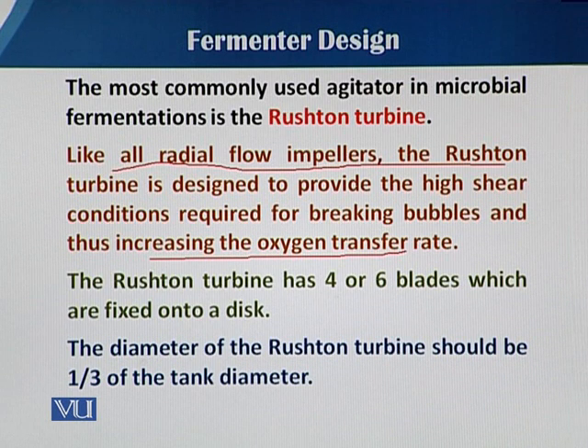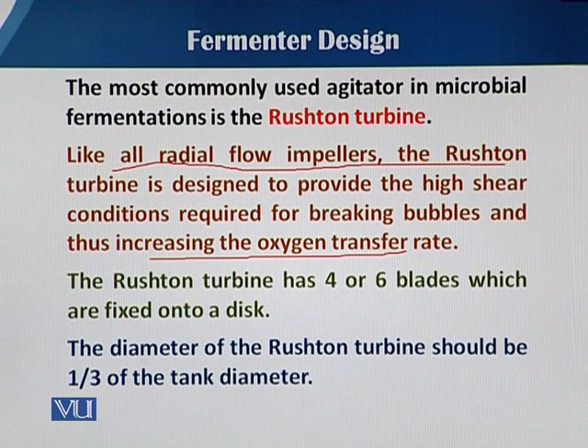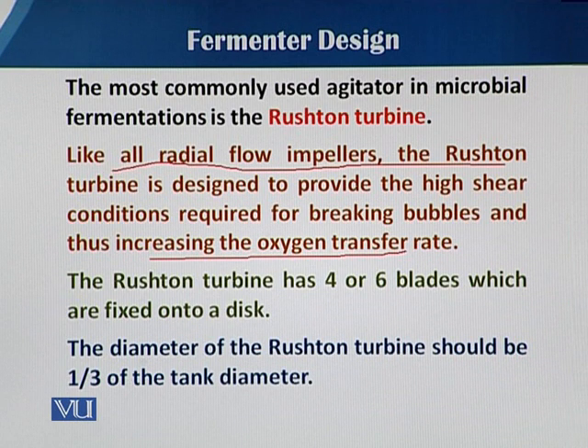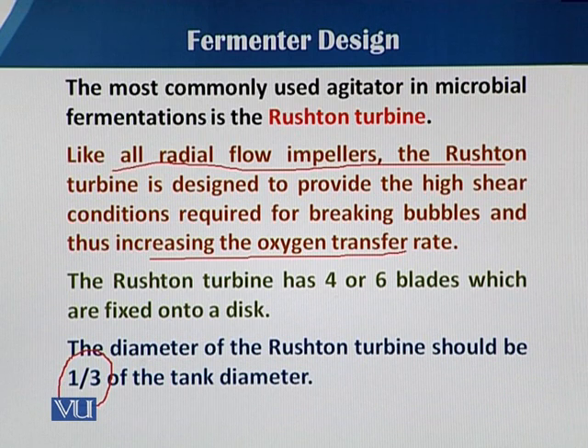In Rushton turbine impellers, the number of blades can be varied from 4 to 6. Some Rushton turbine impellers have 4 blades and some have 6 blades. As we have already discussed regarding the geometrical ratio, the ratio between the Rushton turbine impeller width to the diameter of the fermenter is 0.33 — that is, one third of the total diameter of the fermenter should be the width or the impeller span.